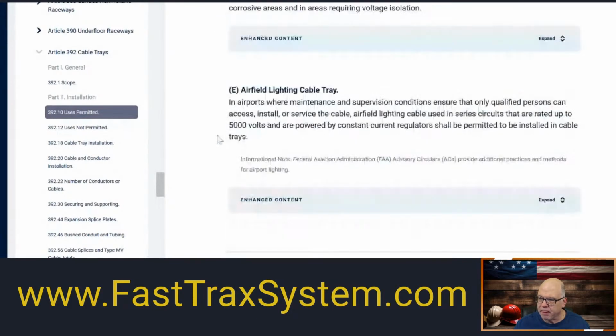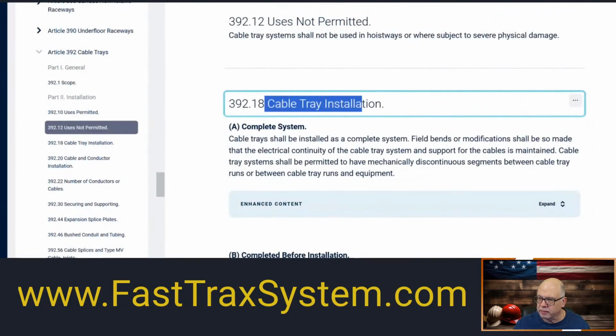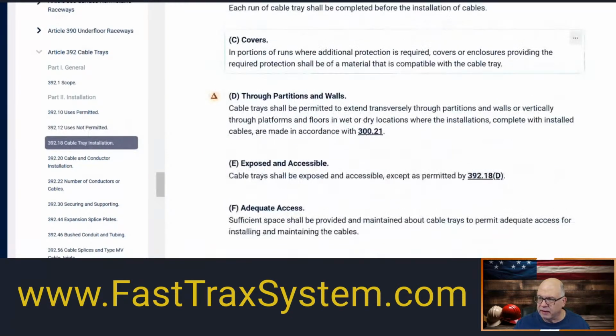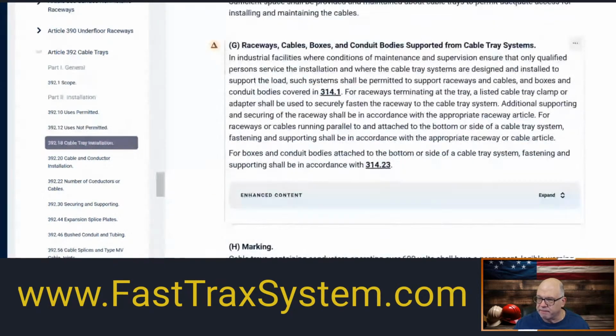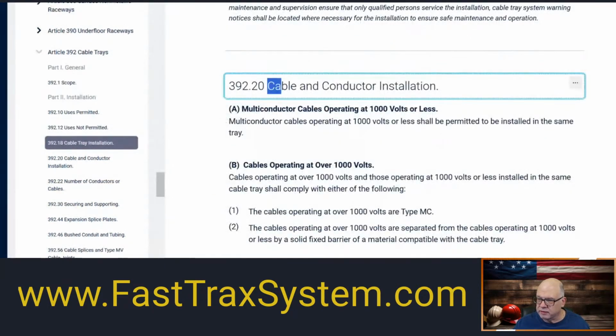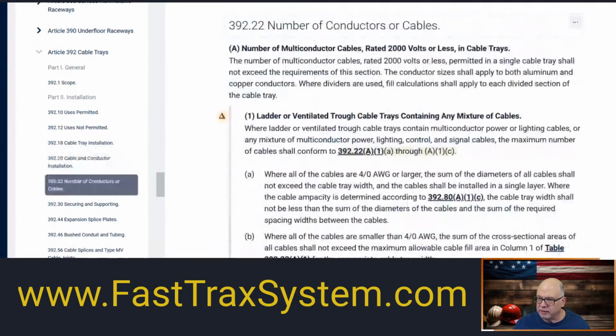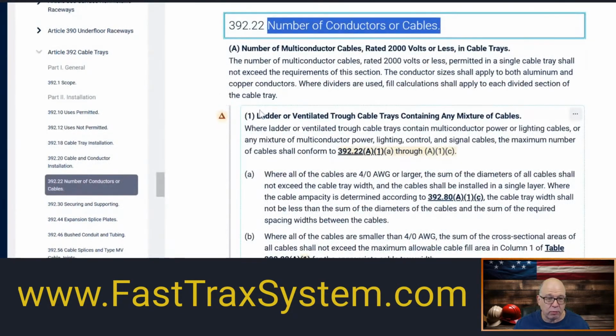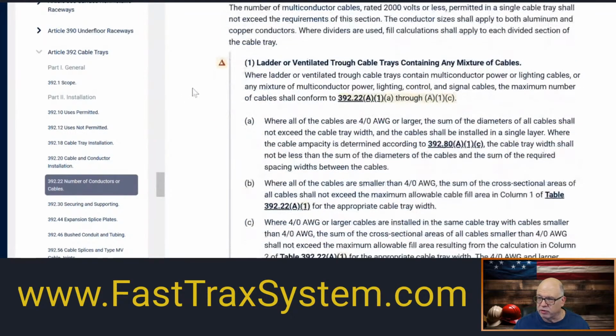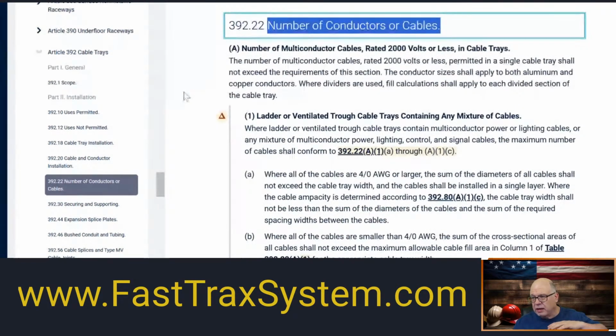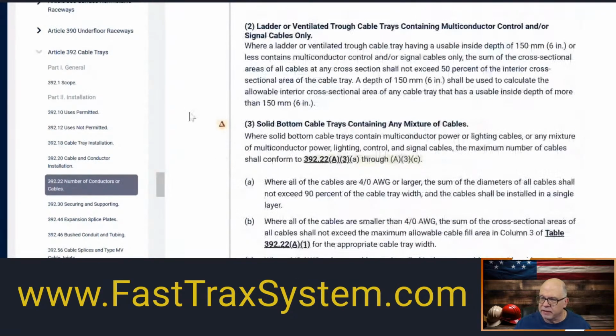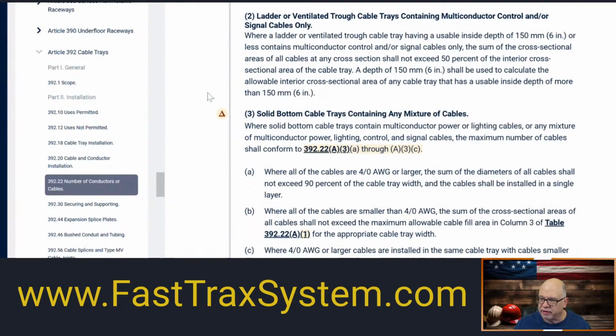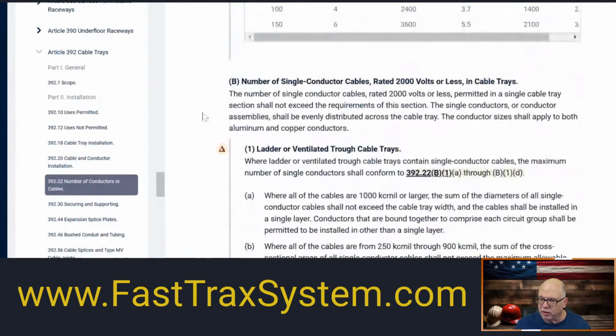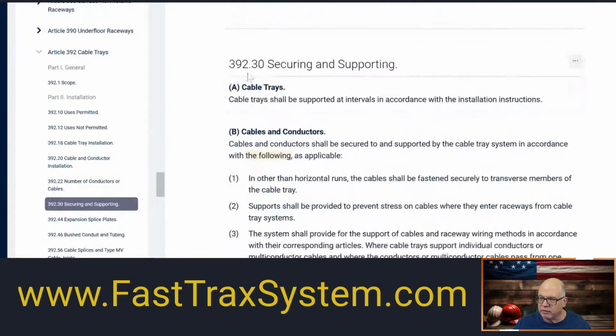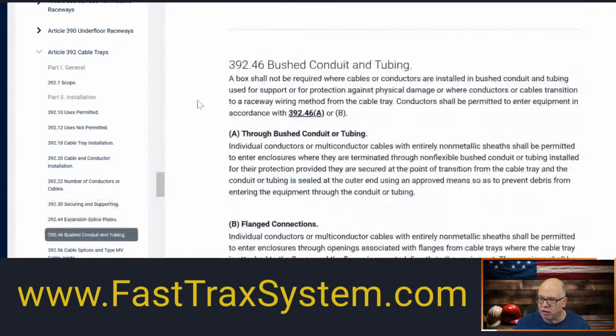okay? Nothing there. Uses, nope. Cable tray installations, okay? But I don't see anything about splices in it, okay? Markings, no. Okay, installation, no. There's a number of conductors in it. Again, that's one of the biggest parts of 392, how you configure them in a tray, whether it's a ladder tray, whether it's solid bottom, things like that. You've got different configurations there. There's a ladder and vented trough type cable tray, but that's nothing about what we're looking for. Keep going down. Securing and supporting wasn't really the question at all.